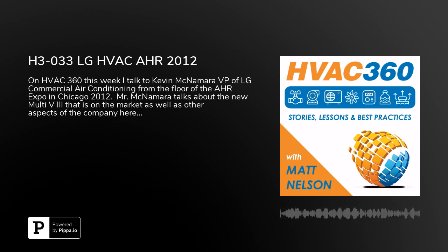So you're actually being proactive and going after that outside air component. If you think about the design part - you've got the cooling, you've got the heating, you lay out the system, that's great, but now you've got to put in the outside air. How do you handle that with a completely different system? But you actually have specific products that address that. That's correct, it's behind that wall right over there. The ECO-V product - I've seen it installed myself in Korea, and we're excited about having it here in the United States now.